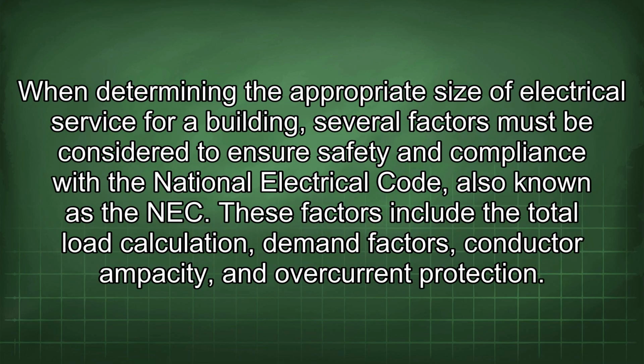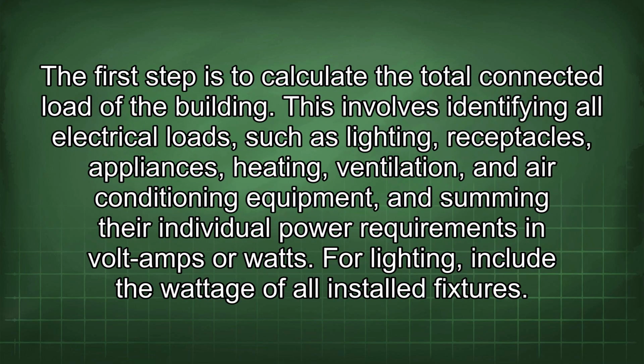When determining the appropriate size of electrical service for a building, several factors must be considered to ensure safety and compliance with the National Electrical Code, also known as the NEC. These factors include the total load calculation, demand factors, conductor ampacity, and overcurrent protection. The first step is to calculate the total connected load of the building. This involves identifying all electrical loads, such as lighting, receptacles, appliances, heating, ventilation, and air conditioning equipment, and summing their individual power requirements in volt amps or watts.